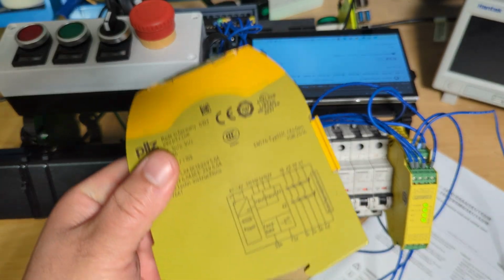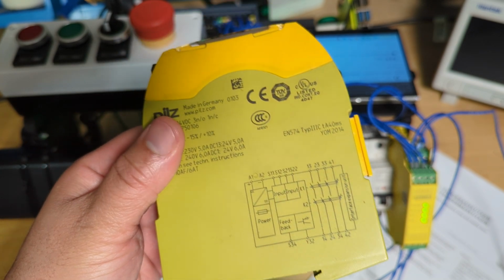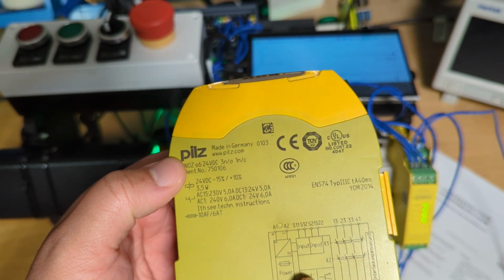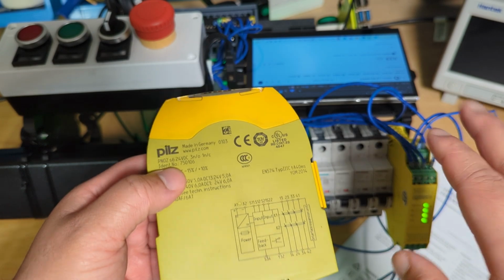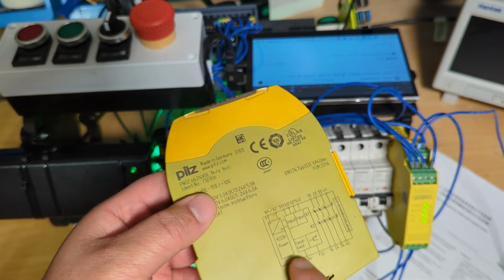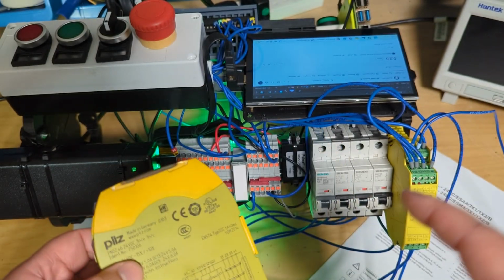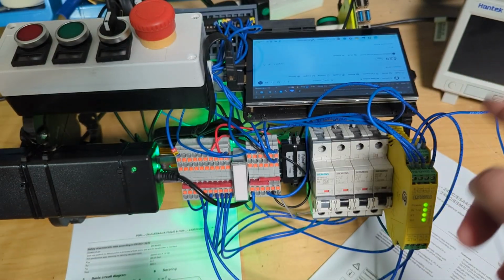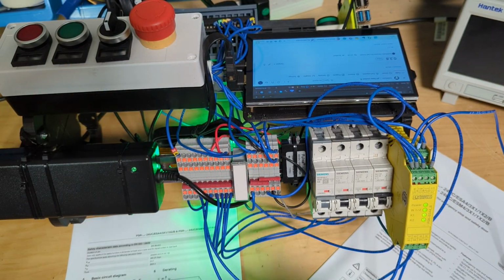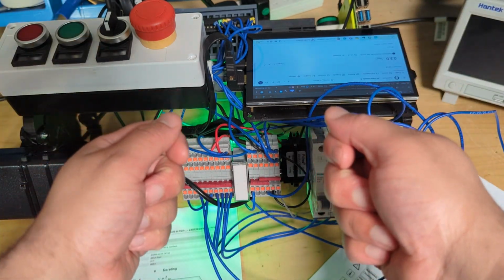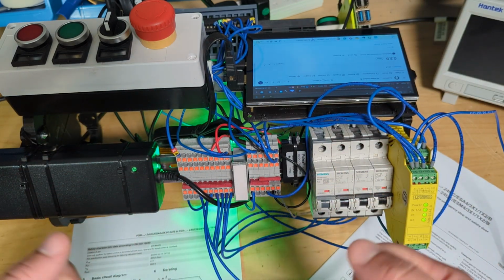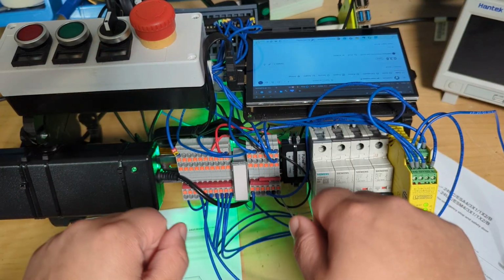This one as well is slightly more complicated in that it's a two-hand operation monitoring safety relay, so be aware of that. You can't use this safety relay for an e-stop circuit. You'd have to use it for a two-hand operation, which is basically when you might have a press and the operator's putting jeans in a press and he stamps it. They have a cage around it and they don't want the operator to be able to put their hand in the machine whilst he's operating it. So you have two buttons, and you press both buttons down.